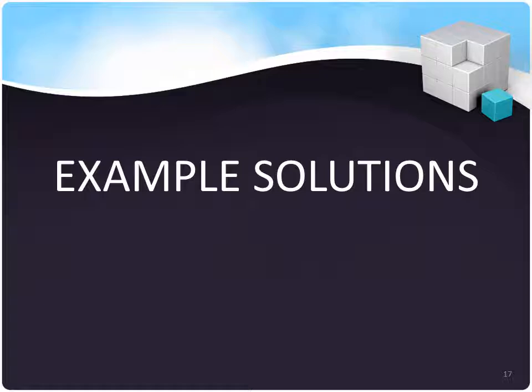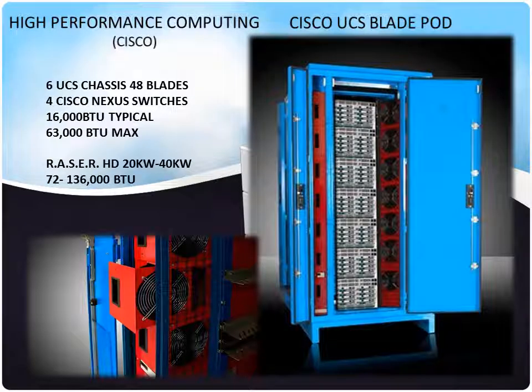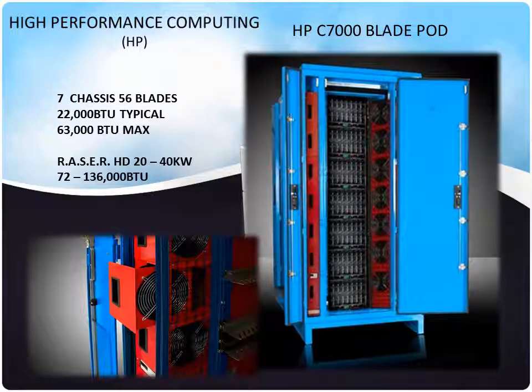Here are some example solutions using our MMDCs coupled with IT equipment to produce an appliance. This is an example of high-performance computing using Cisco blade pods: 6 UCS chassis, 48 blades, Nexus switches — they put out a lot of BTU and can be integrated into one R.A.S.E.R., showing up pre-configured and ready to be plugged in. This is an example using HP blade C7000s, some of the hottest and most powerful servers on the market. Normally it would require a building to handle this kind of heat load, but we can handle it in under 16 square feet with a small detached air-cooled chiller.